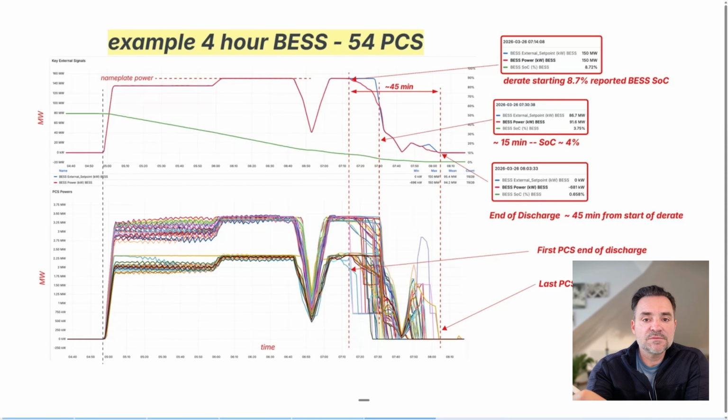There's an attempt to try to discharge a bit more, and then you could see that at this point, the red line is what we could deliver. We're not able to deliver that. So it means the actual available power at that time was like the red line here. The behavior of the dispatch, the set point, will highly depend on who controls the BESS, their control algorithm. You don't really know how this is going to behave.